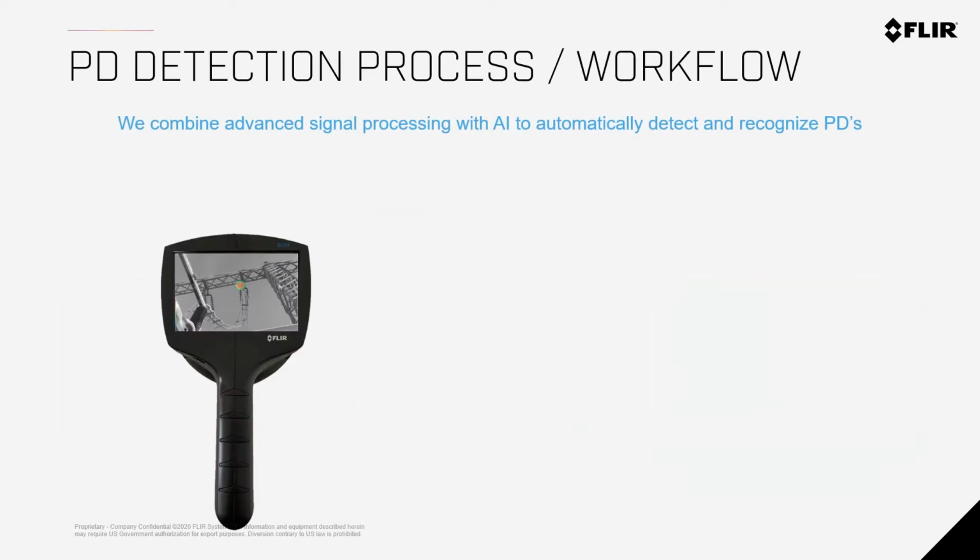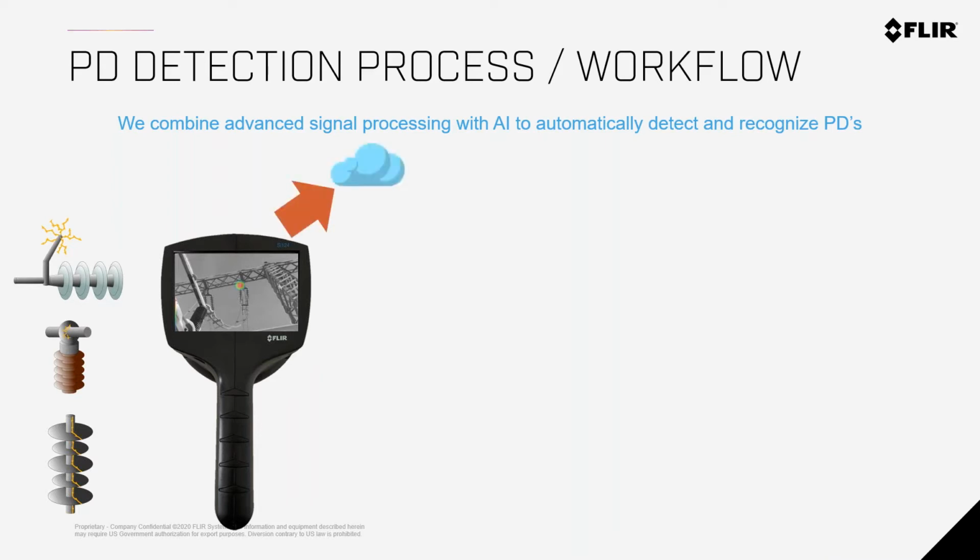So with our camera, when we're looking for partial discharge, you do a couple of things. One, you point the camera at the different equipment in your substations, your power lines, your transmission lines. This camera can work up to over 300 feet. So you find a problem, find that image, you take a picture of it. It goes up to the cloud, as we all like to say.